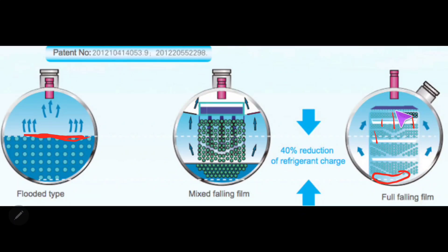It has spray rails up top that you'll have your actual refrigerant injected through the liquid line inside the top of the evaporator, and it's going to distribute that liquid across the whole length of the heat exchanger. Whereas on a flooded type, our liquid is coming into the bottom side and just kind of gets distributed. Most of the time there'll be some form of distribution plate in there, but its job is just to fill up from the bottom side.